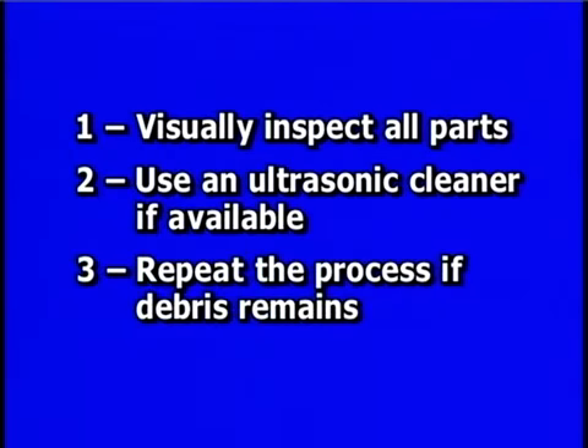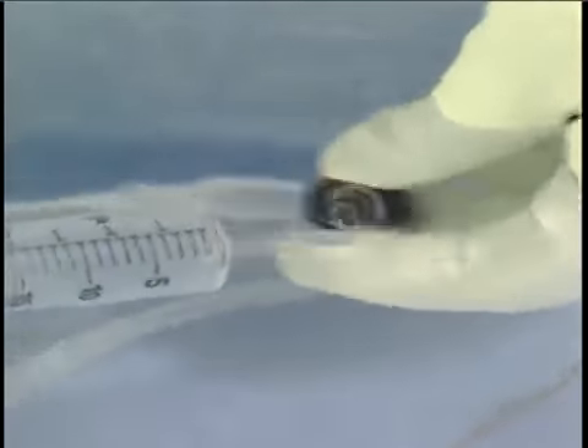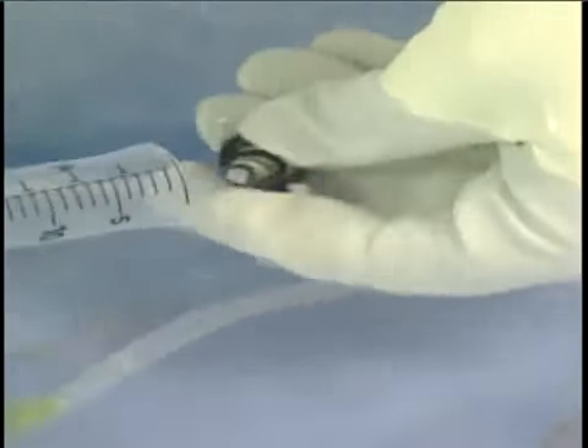If any debris remains, ultrasonically clean the parts at 40 kHz for 5 minutes. If an ultrasonic cleaner is not available, place the components back into the detergent solution and repeat manual cleaning. While immersed in the rinse water, flush the valves and the air-water channel cleaning adapter. Depress and release the pistons while flushing.